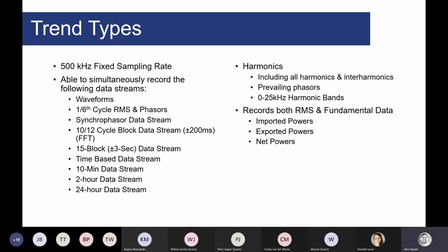The device can measure current, voltage, and harmonics and interharmonics, and this is carried out every cycle. The basic measurement time interval for the instrument is 10 or 12 cycles, depending on the frequency of your power system. The instrument samples at 500 kilohertz, and using these 10-12 cycle time intervals, we aggregate the values to get different data streams.